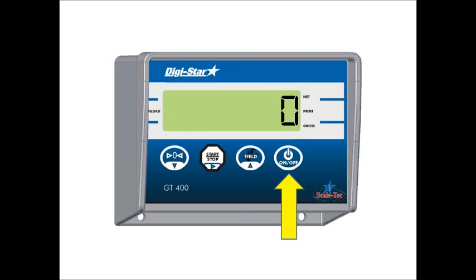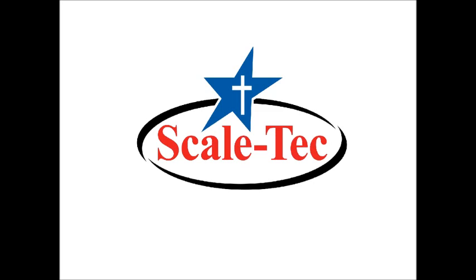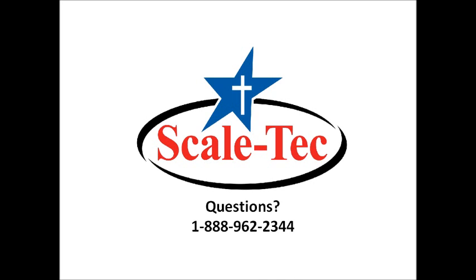Then we'll press the on off button, which will store the calibration number and return it back to the weighing mode. If you have any questions, please call us at Scale-Tec at 1-888-962-2344.